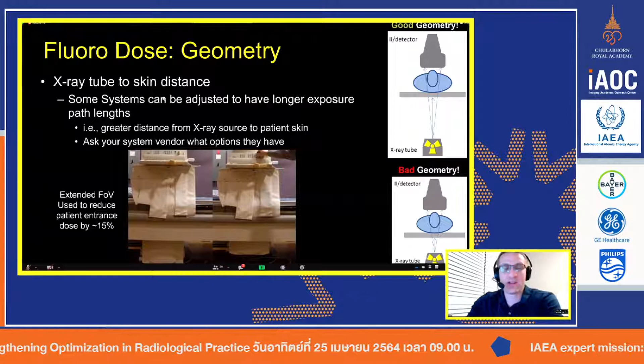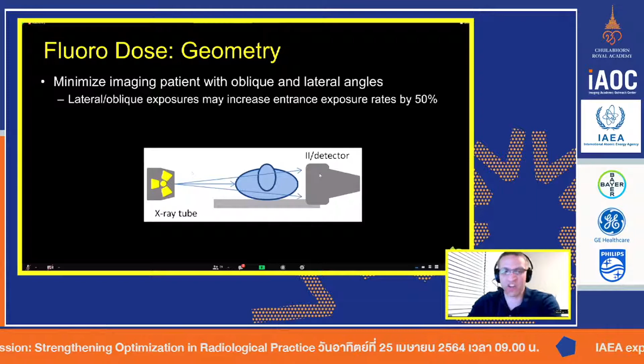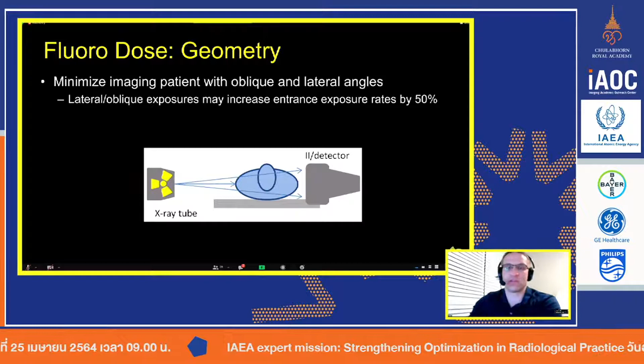You want to minimize the angles where you're passing through a large portion of the patient's body. So you want to minimize lateral projections and oblique projections when you have a rotating C-arm. The reason for this is obviously because if the machine sees there's more attenuation or more tissue between the tube and the detector, that means the machine's going to have to turn up the radiation output. So therefore, the skin's going to get more dose. It's simple. If we're thicker this way, it needs more radiation. We're the thinnest, typically anterior to posterior. So as we keep the beam more aligned along the thin geometry of our body, then we're just safer. It's safer for the patient.